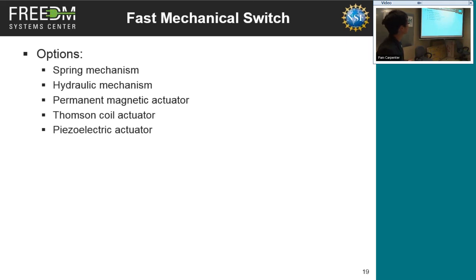Then there's the permanent magnetic actuator, which is a newer design, primarily used in medium voltage level vacuum circuit breakers. It has reduced the moving parts significantly, but because of the operation principle, it's still kind of slow. And there are Thomson coil actuators. This is the actuator we are trying to optimize and is used in our design. And there's also something called a piezoelectric actuator. We have a partner team at Florida State working on a mechanical switch based on a piezoelectric actuator. So potentially it also has the capability to operate in about 1 millisecond.